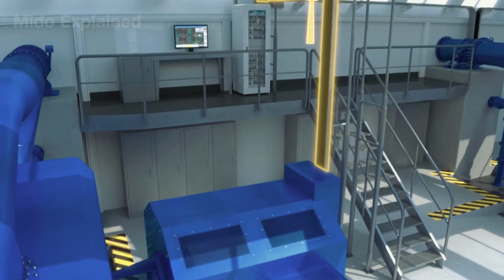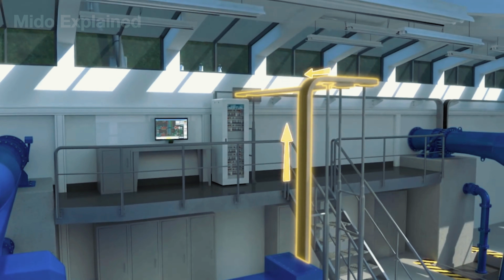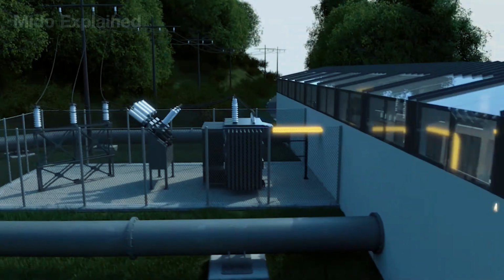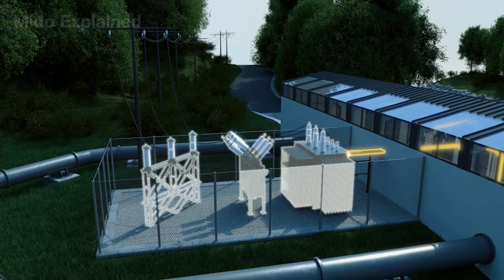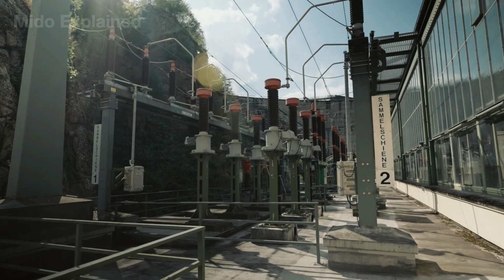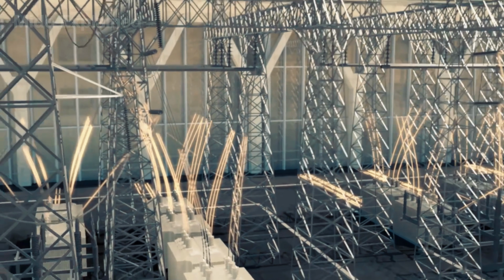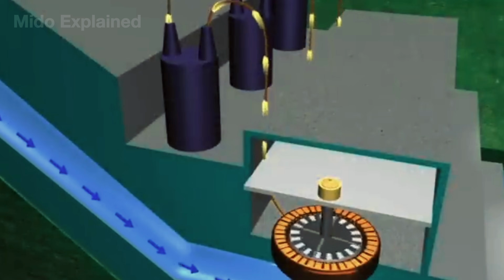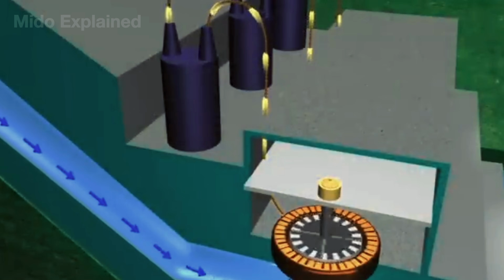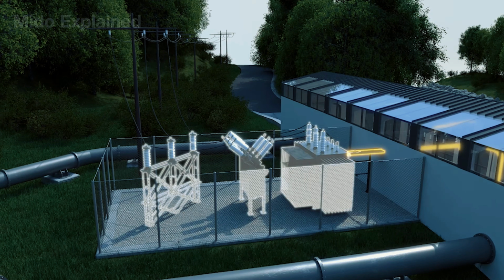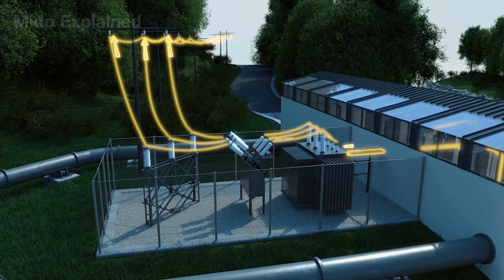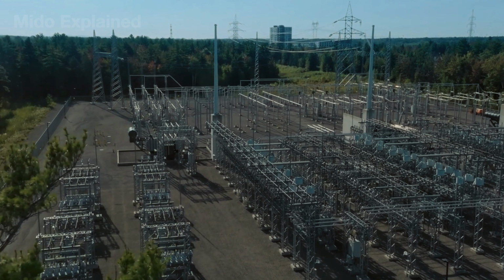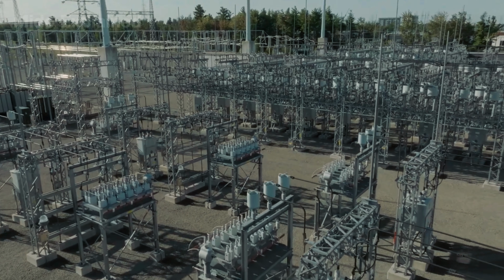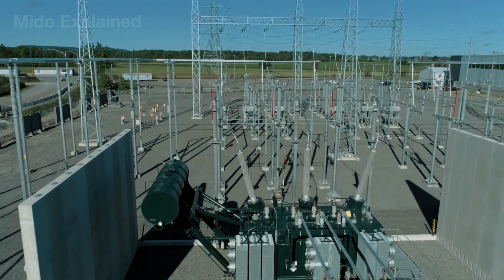However, the electricity just generated cannot yet be transmitted far. Before being integrated into the national power grid, it must pass through another crucial device, the transformer. If electricity is fed directly into the power lines, a significant portion of the energy is lost as heat due to the resistance of the conductors. To minimize this loss, the current is first passed through a transformer, which increases the voltage from the few tens of kilovolts generated by the generator to very high voltages such as 110, 220, or 500 kilovolts, depending on the transmission system of each country.